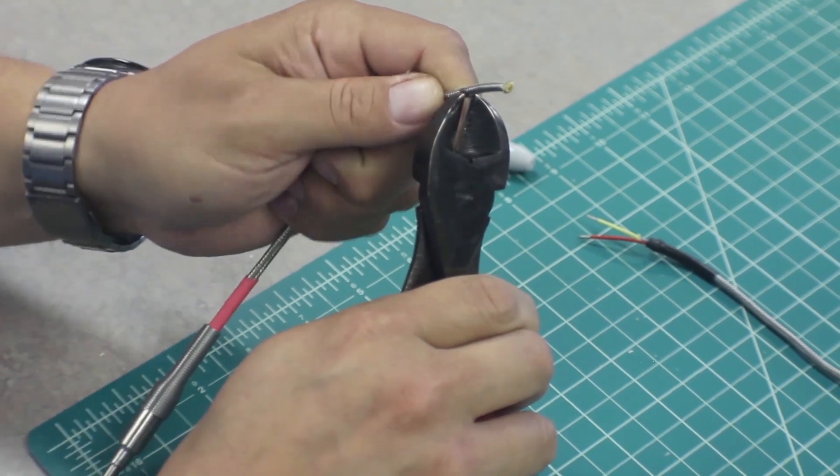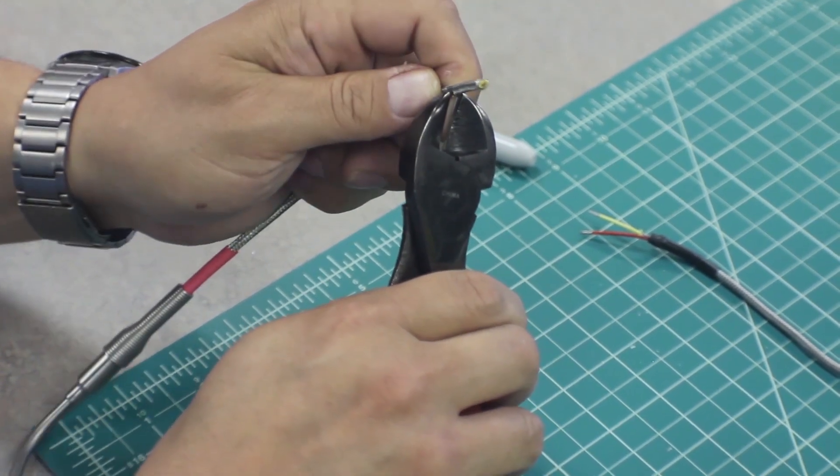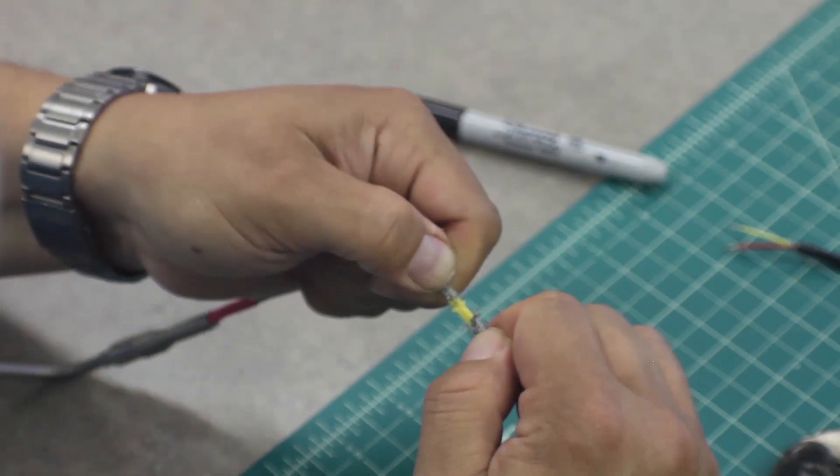Next, using the diagonal pliers, starting at the second mark, carefully trim and remove the stainless steel outer braiding. Take extra caution not to nick any of the internal wires. This can cause a short or reading errors.